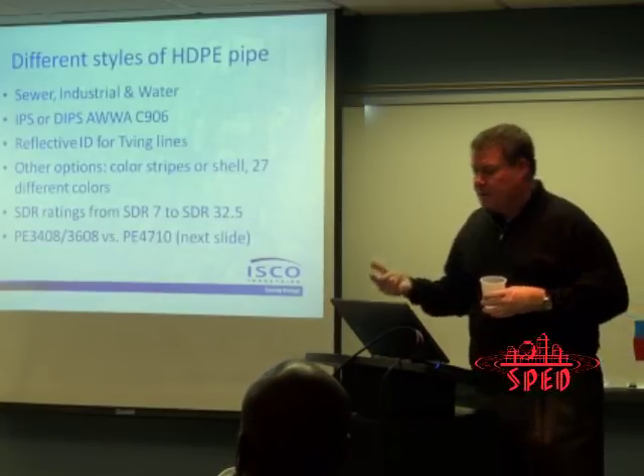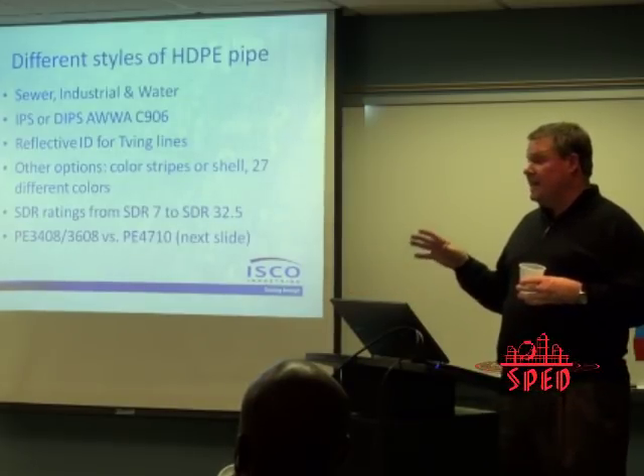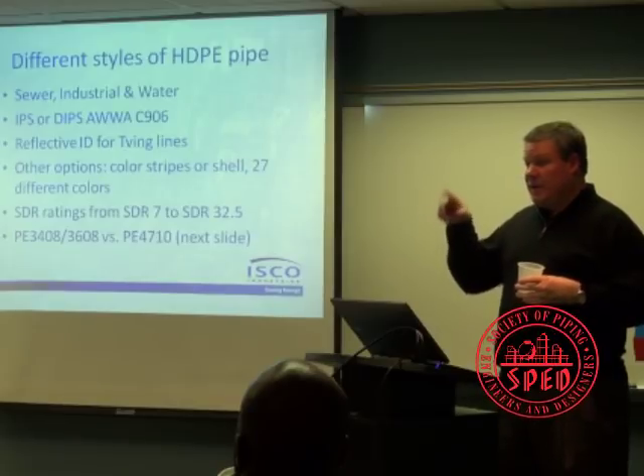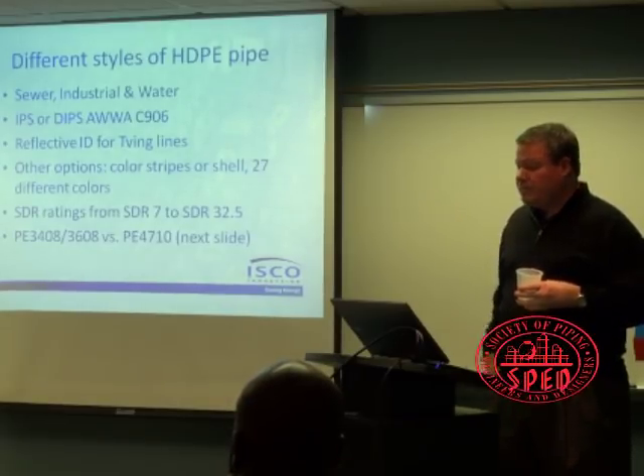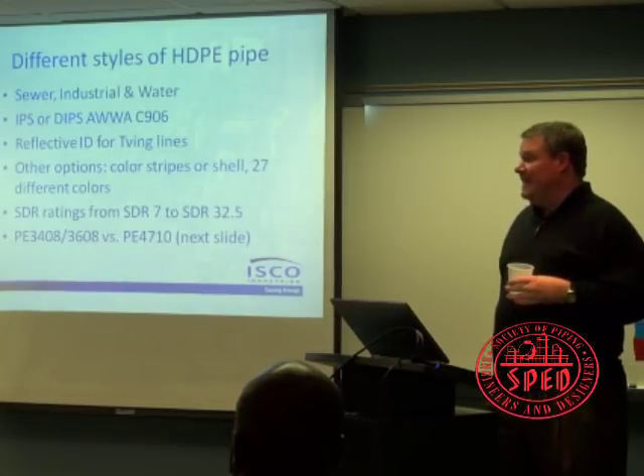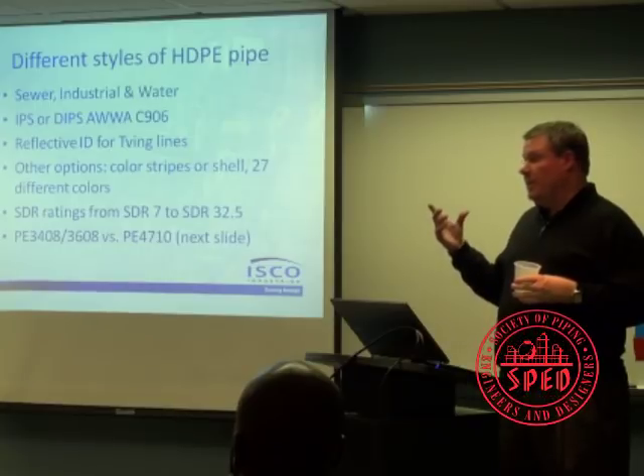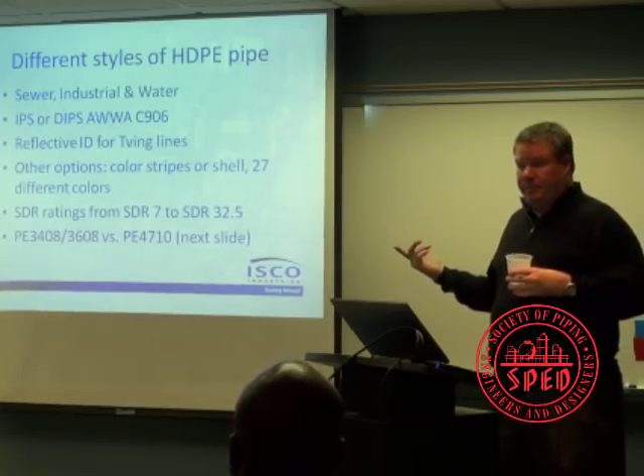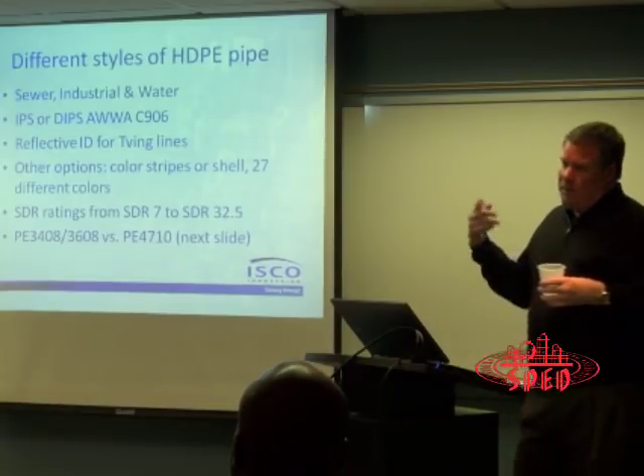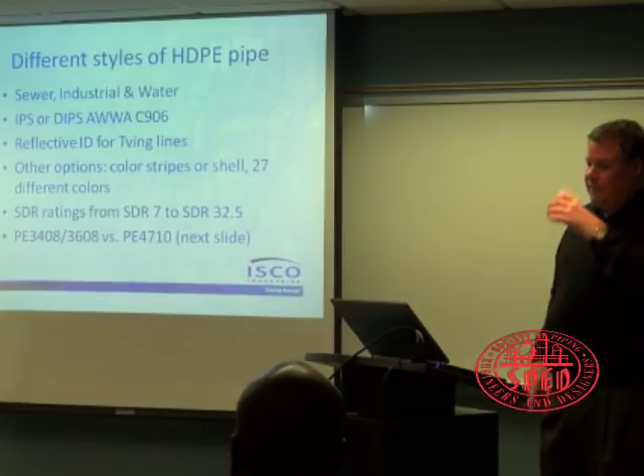So different styles of polyethylene. There's sewer grade, industrial water grade. We can get iron pipe size, we can get ductile iron pipe size, AWWA. So the same OD as ductile iron pipe, same OD as iron pipe size. We have reflective IDs, so that if you want to TV the line constantly, we can give you what we call an Oreo cookie. White interior, black shell. You shine a light on a black hole, it's still black. It's pretty tough to see, so we can do white if you want to.